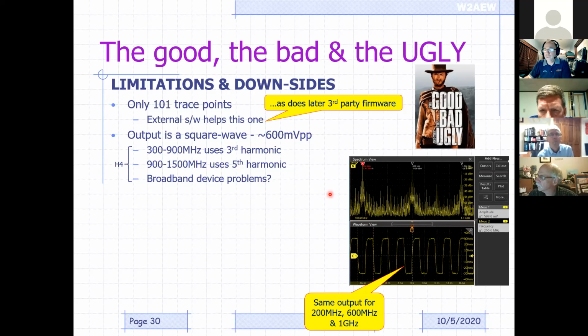For example, on the scope trace that I've got down here, this square wave that you see in the time domain view is, again, about 600 millivolts peak to peak at 200 megahertz. That's the same output that I would get if I told it to measure at 600 megahertz or at 1 gigahertz, right? Because the 600 meg is using the third harmonic of that, and the 1 gig is using the fifth harmonic. And this is the frequency domain view of that signal. So there's the fundamental at 200, the third harmonic at 600, the fifth harmonic at 1 gig.